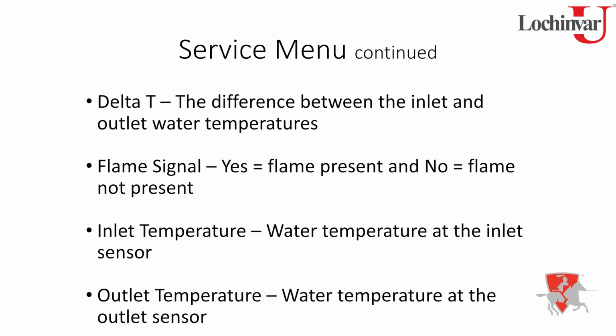Flame signal, unfortunately, like I said, doesn't give you a number. It just says yes or no. Well, guess what? If it's running, you know you've got a flame signal. So that's kind of redundant. It doesn't make a whole lot of sense, but it's there. You can also see your inlet and your outlet water temperatures. So you can see those individually as well.